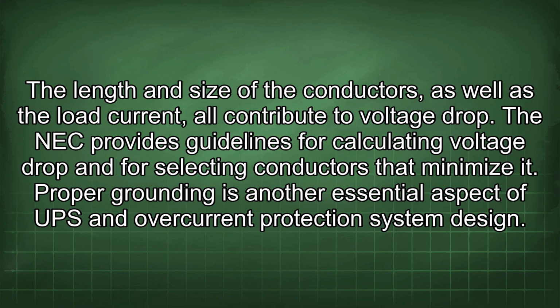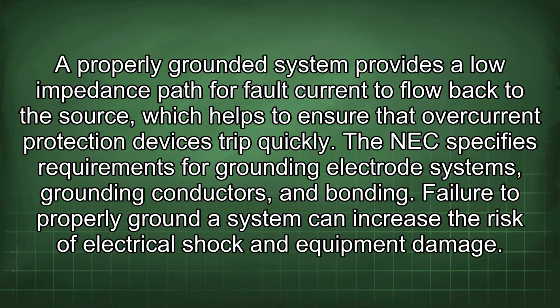Proper grounding is another essential aspect of UPS and overcurrent protection system design. A properly grounded system provides a low impedance path for fault current to flow back to the source, which helps to ensure that overcurrent protection devices trip quickly. The NEC specifies requirements for grounding electrode systems, grounding conductors, and bonding. Failure to properly ground a system can increase the risk of electrical shock and equipment damage.